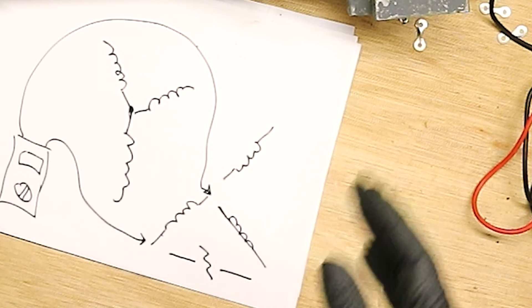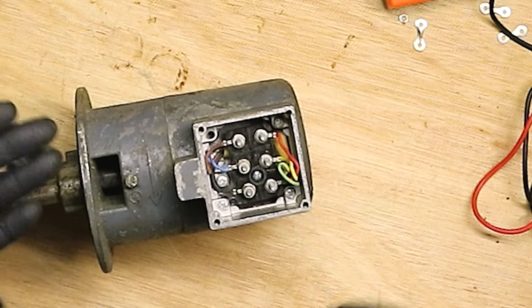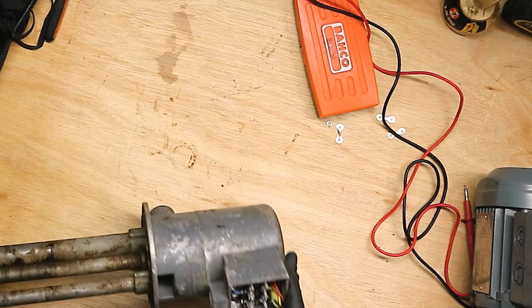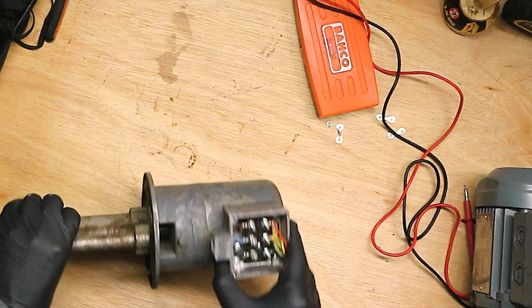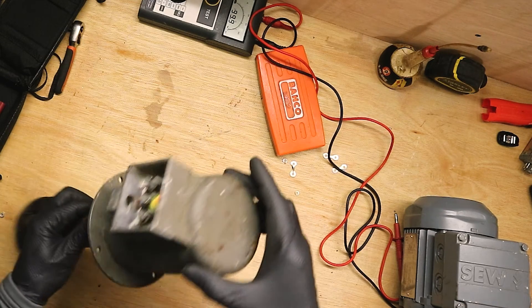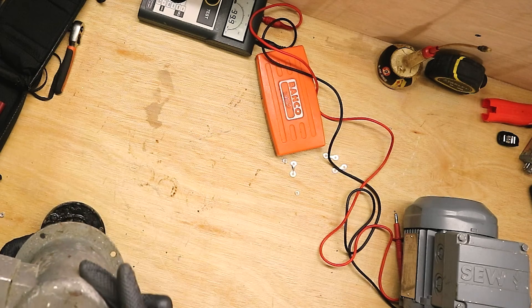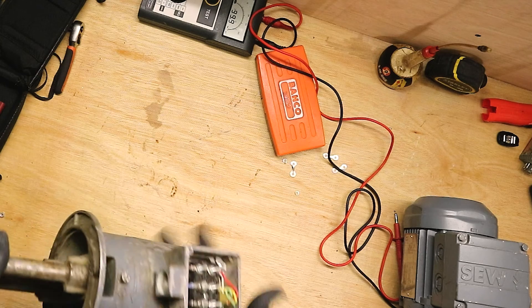So something's happened to this motor, and we have lost the continuity. Something's severed the windings internally. It could have been overheated. It could have been mechanical damage where it's moved and severed it. I would like to be able to remove the casing from this motor, and show you inside. But, I can't see an easy way of doing that.